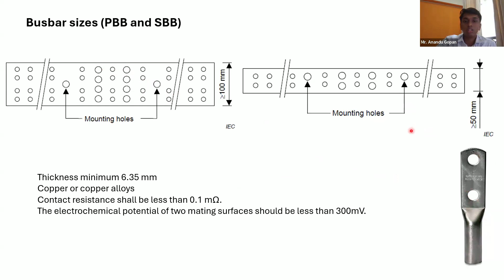And if it is the same metal, there are no issues of electrochemical potential between these two surfaces. If it is going to be separate surfaces, different materials, it should be less than 300 millivolts. And then the crimps which you are going to be using at these locations will look somewhat like this. There are different sizes of these crimps, and these crimps are two-hole lugs, and you are supposed to connect to both of these.